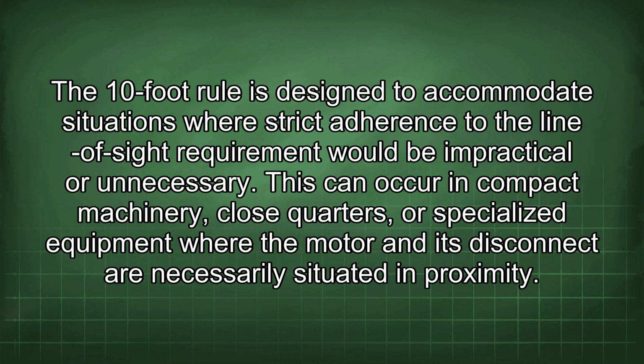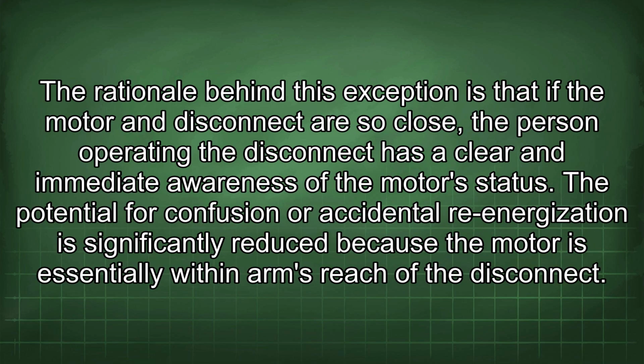The 10-foot rule is designed to accommodate situations where strict adherence to the line of sight requirement would be impractical or unnecessary. This can occur in compact machinery, close quarters, or specialized equipment where the motor and its disconnect are necessarily situated in proximity. The rationale behind this exception is that if the motor and disconnect are so close, the person operating the disconnect has a clear and immediate awareness of the motor's status.